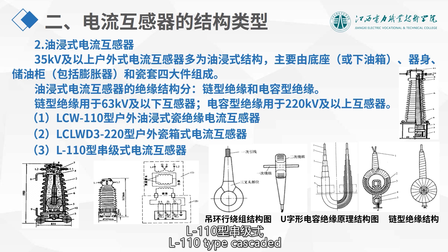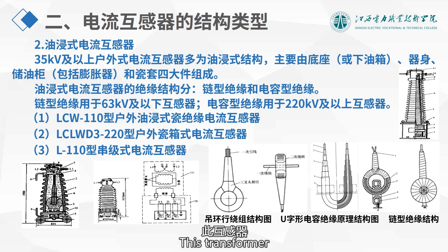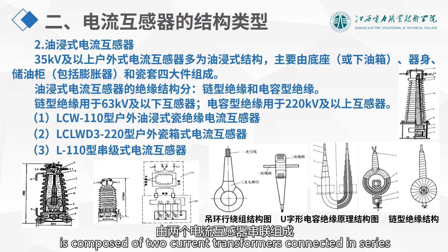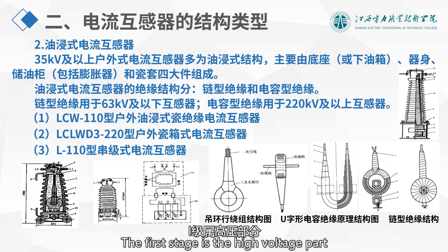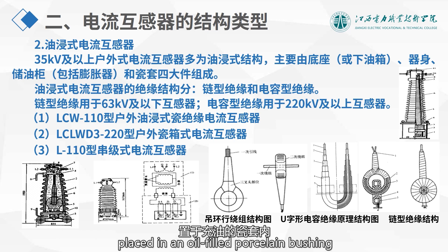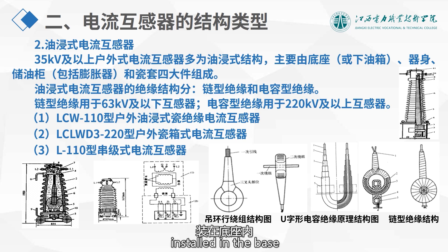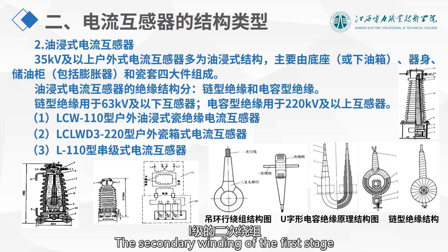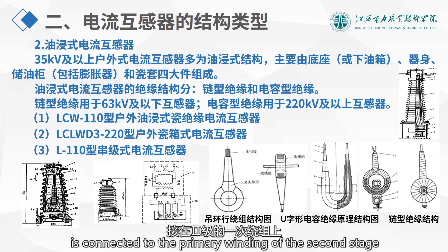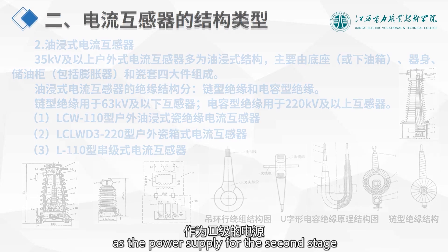The L110 type cascaded current transformer is composed of two current transformers connected in series. The first stage is the high voltage part placed in an oil-filled porcelain bushing. The second stage is the low voltage part installed in the base. The secondary winding of the first stage is connected to the primary winding of the second stage as the power supply for the second stage.